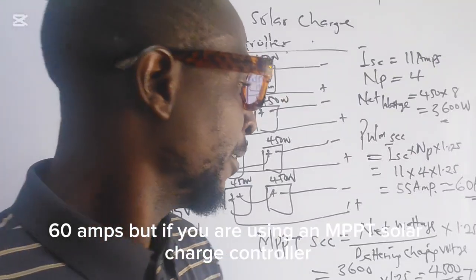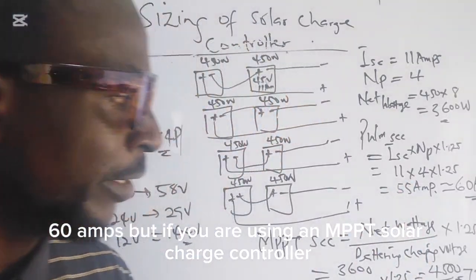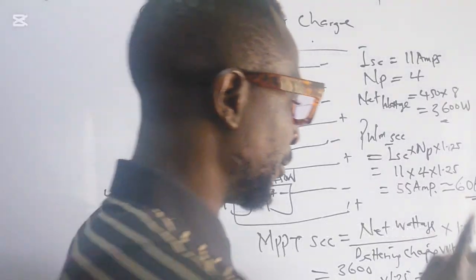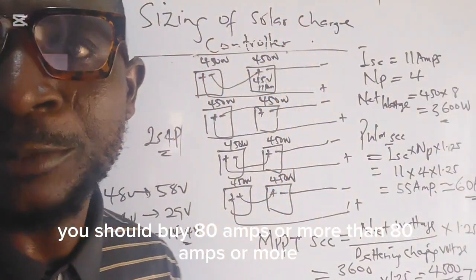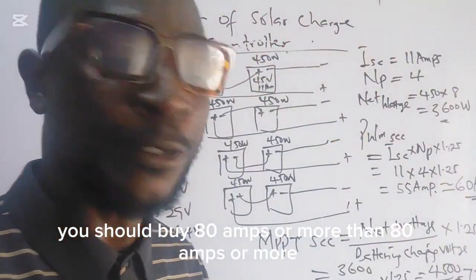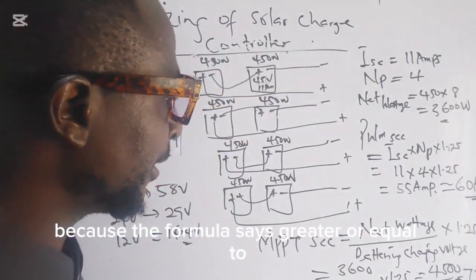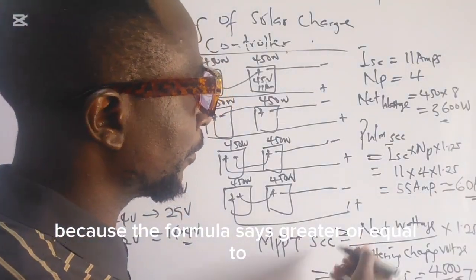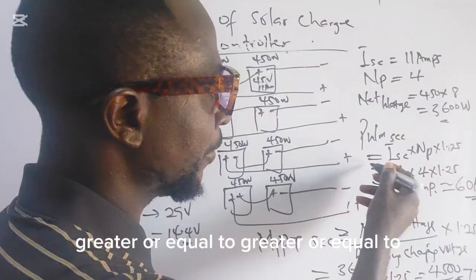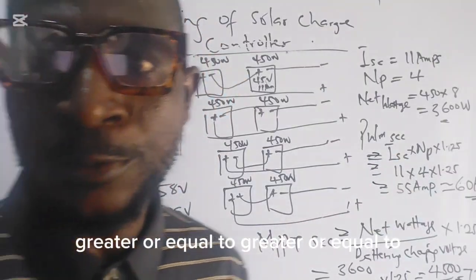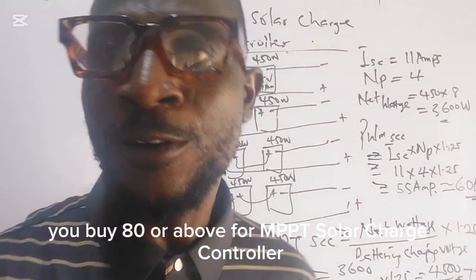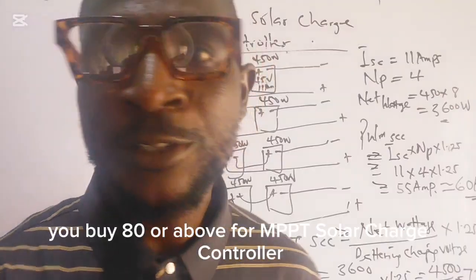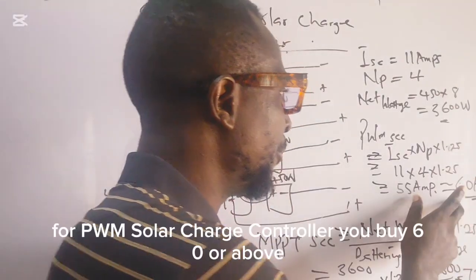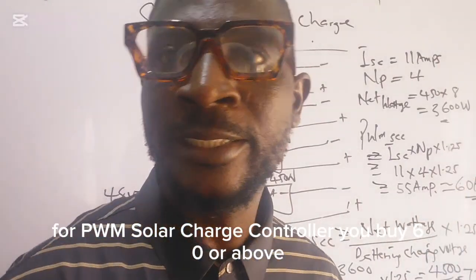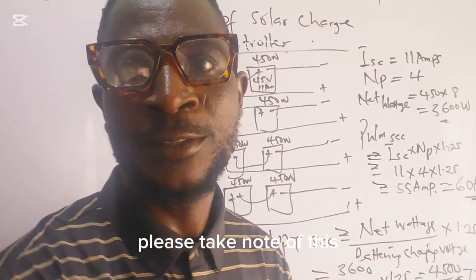But if you are using an MPPT solar charge controller, you should buy 80 amps or more, because the formula says greater or equal to. You buy 80 or above for MPPT solar charge controller. For PWM solar charge controller, you buy 60 or above. Please take note of this.